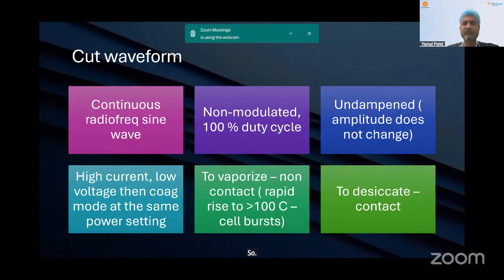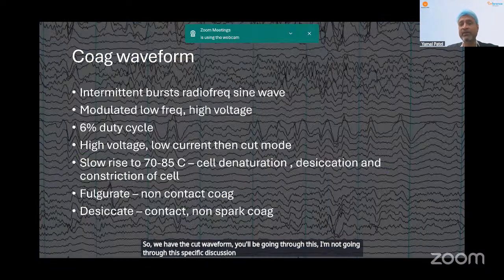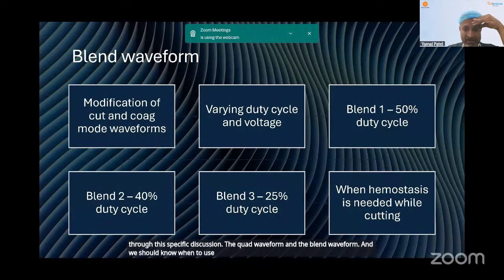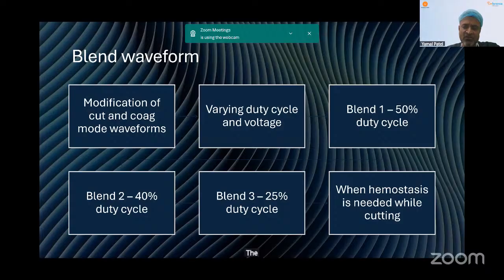So we have the cut waveform. You'll be going through this. I'm not going into specific discussion of the cut waveform and the blend waveform. We should know when to use which one, because they are not to be used interchangeably. And definitely, please do not use blue to coagulate and yellow to cut. I think that is a misnomer. The blue button does not mean coagulation effect. It is the coagulation waveform. Please make this difference very clear.